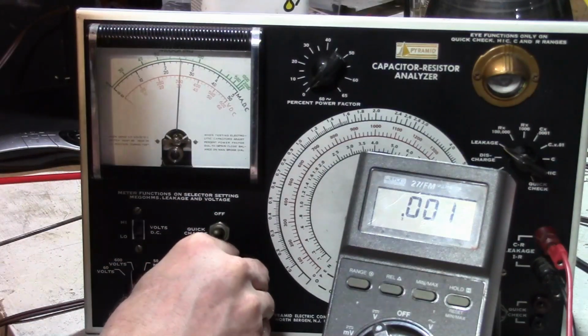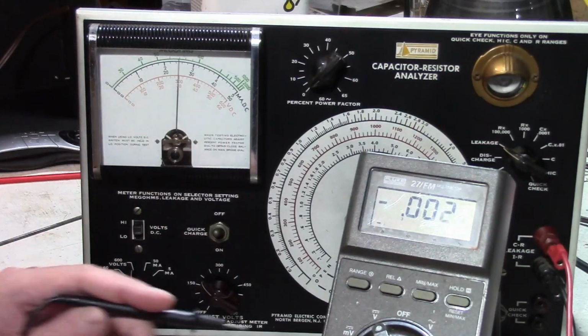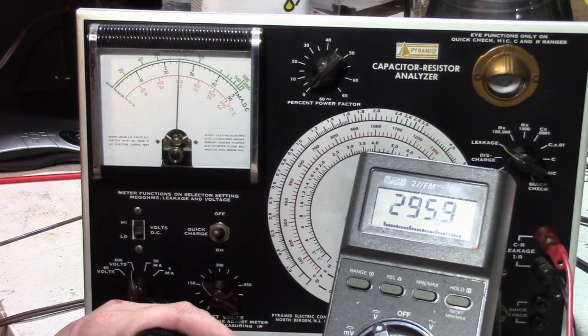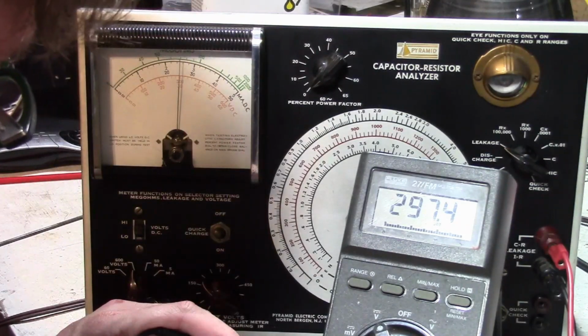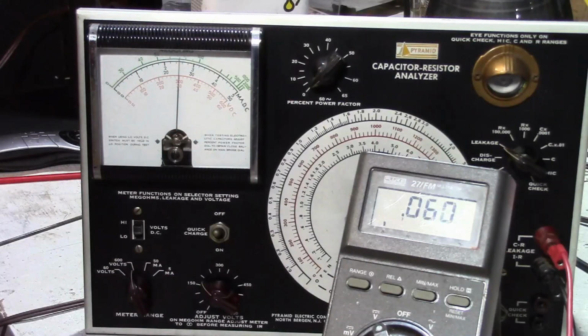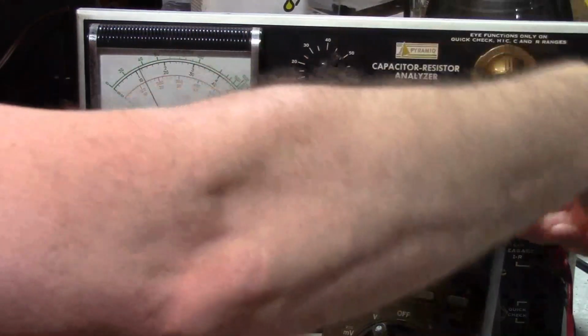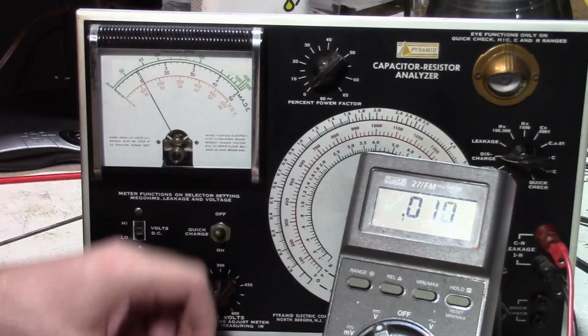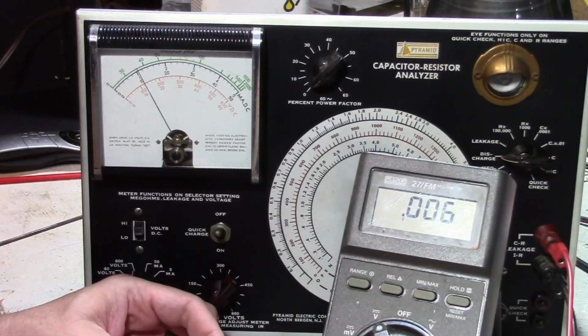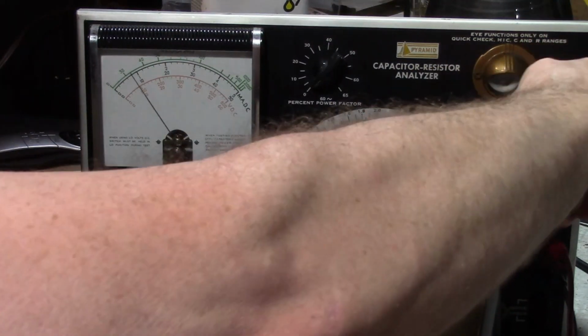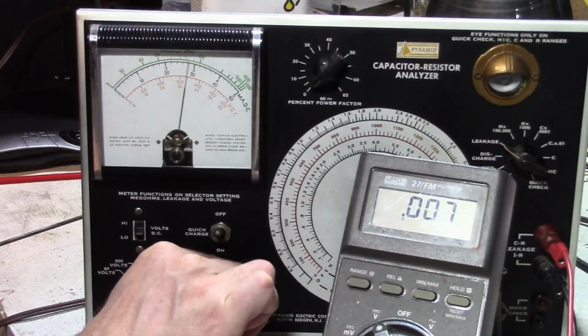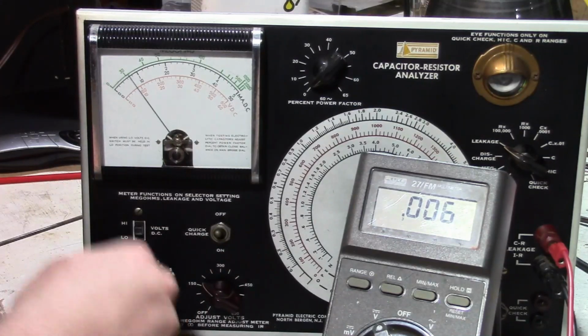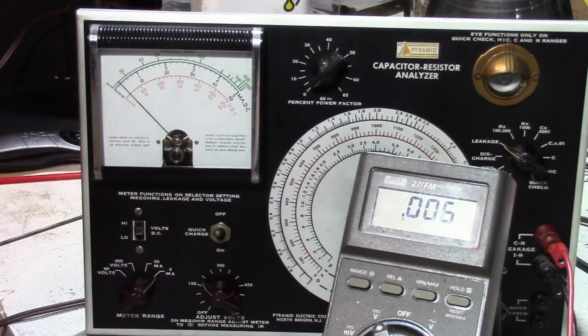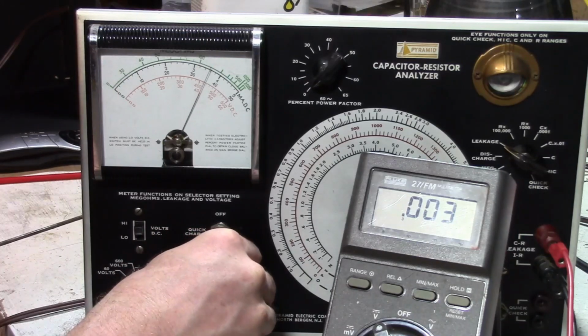And just to show you how accurate this thing is, let's get this back on. I'll set this for 300-ish. Put the voltmeter on there. 295, 296, so 297. That meter is pretty darn accurate. Charging as I pulled it out. Let's try the 47. And we go back to leakage mode. And let's go up to 300 volts. Current. It's already well below 1 milliamp. 450.